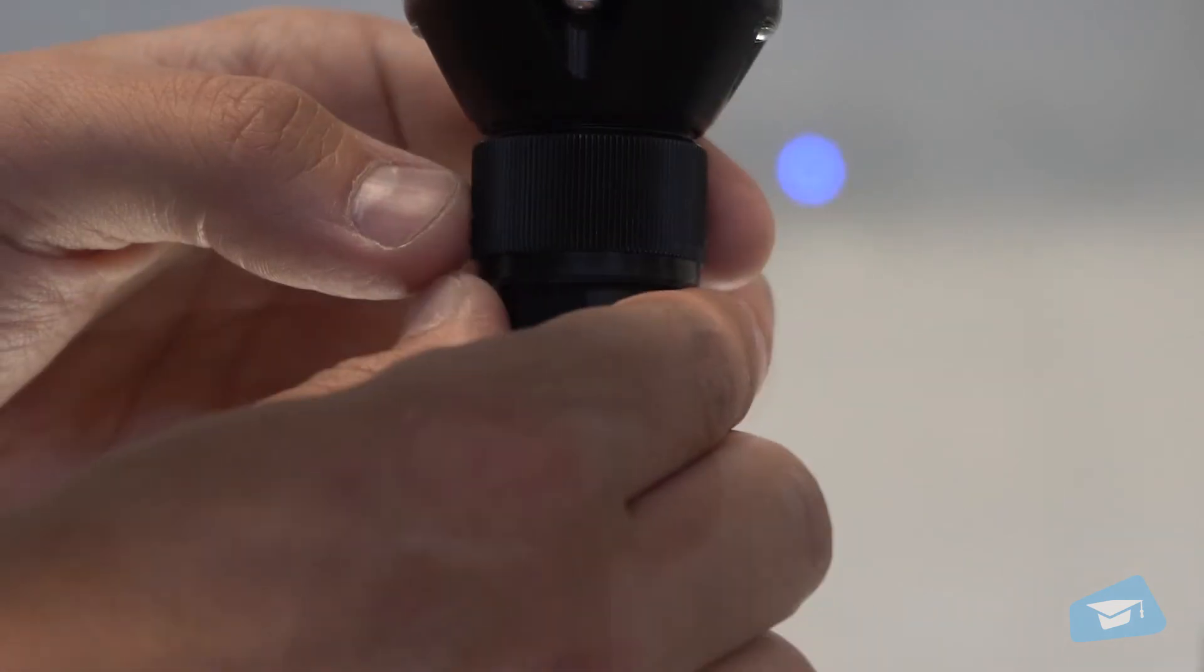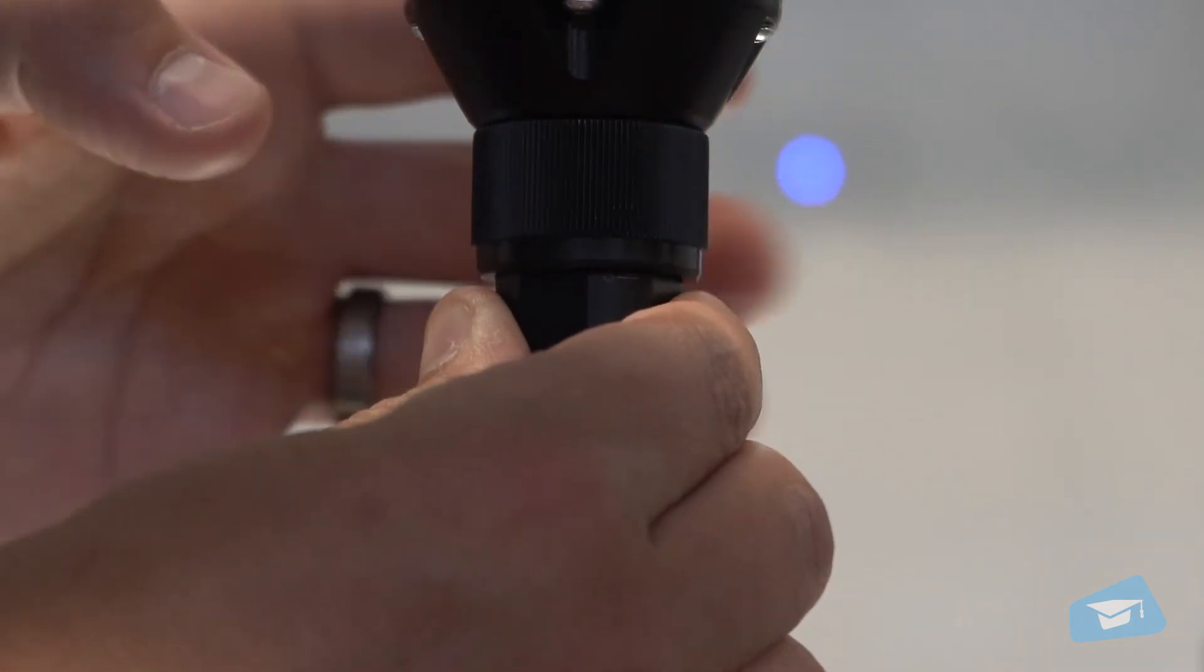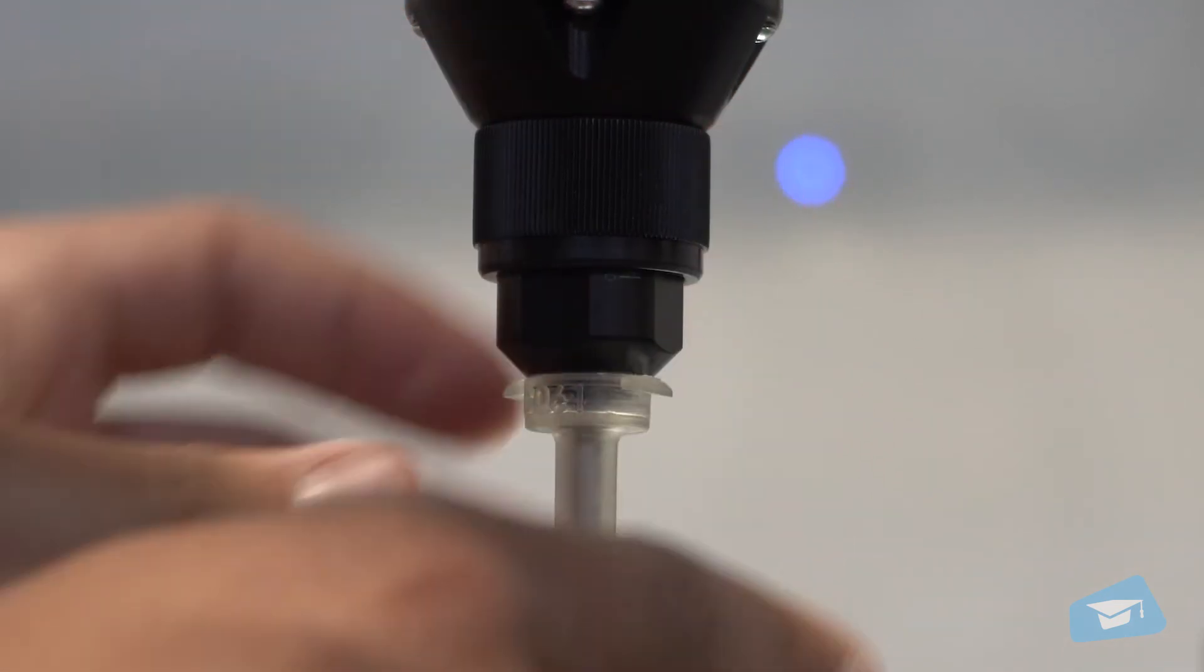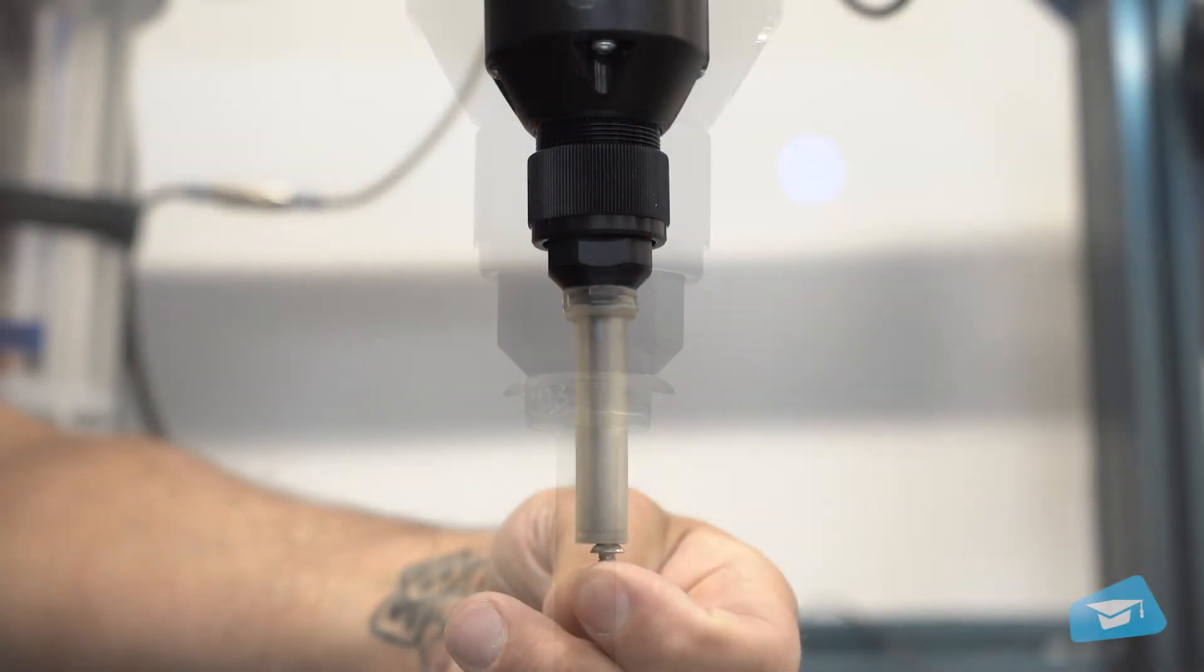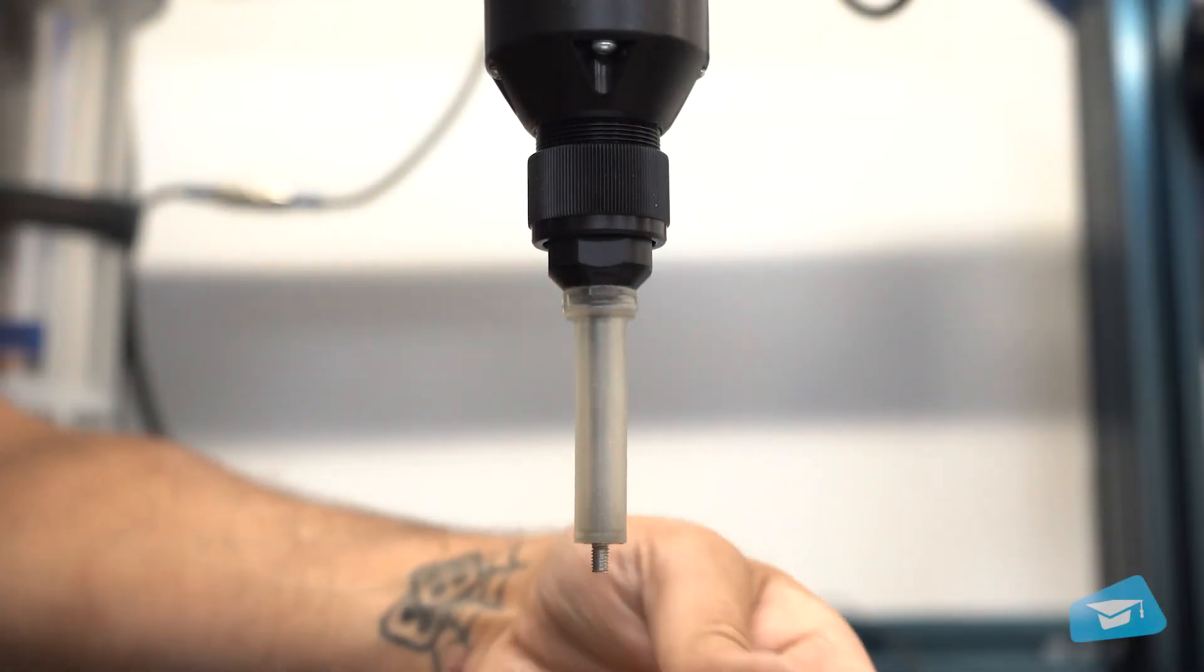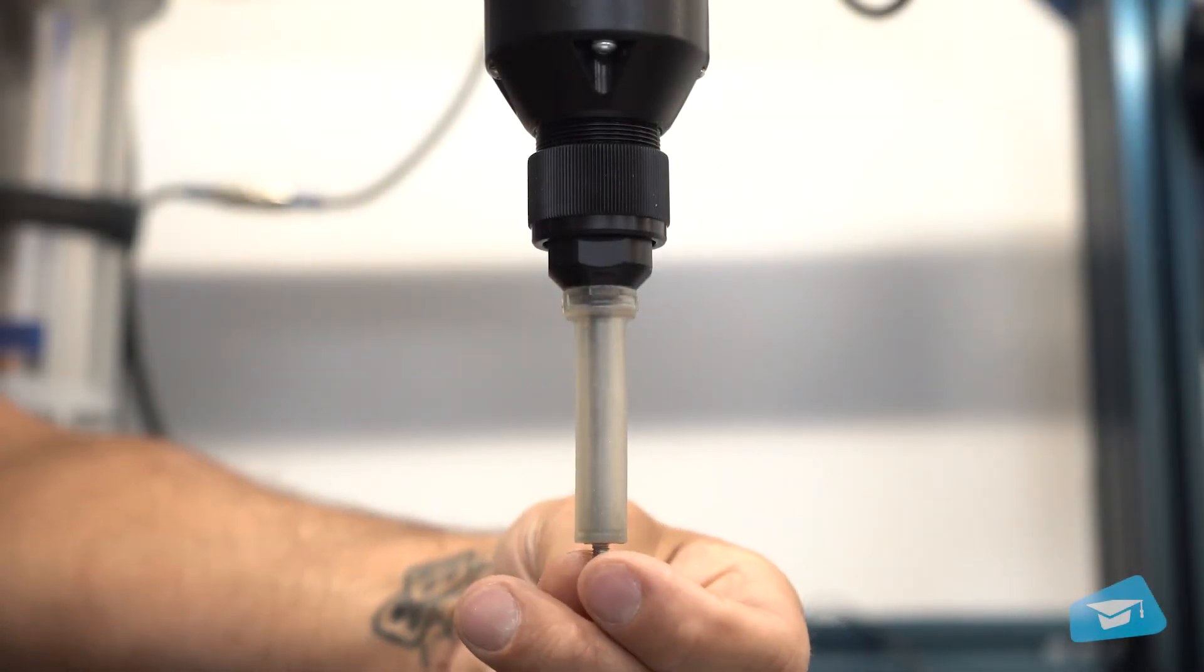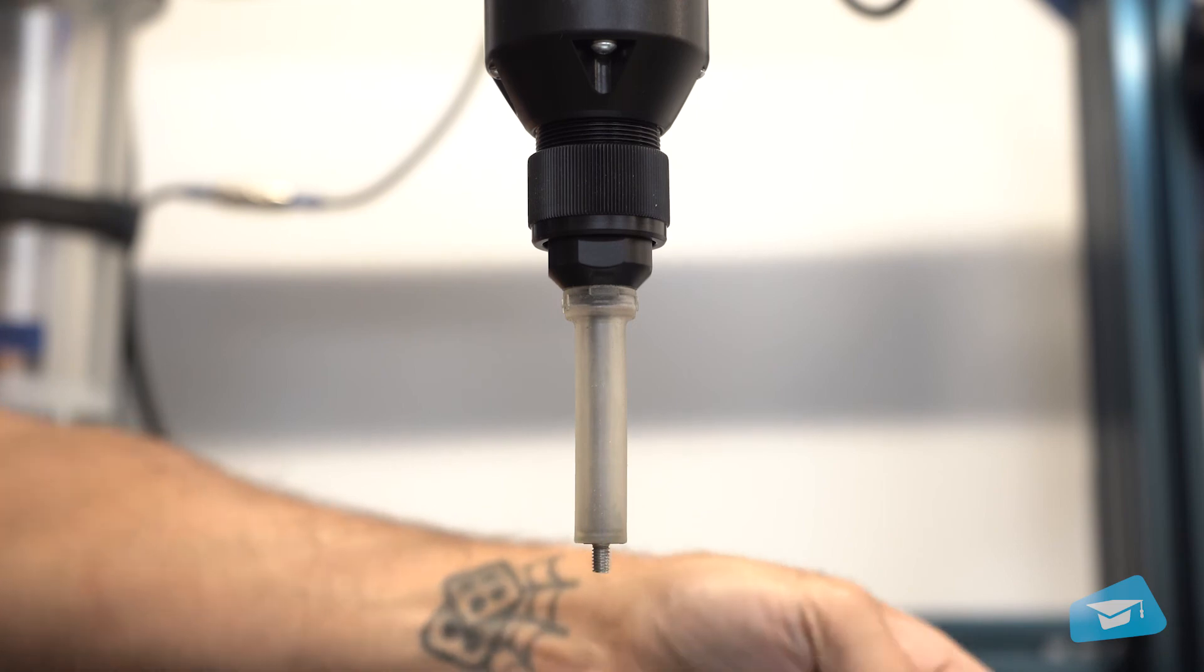Tighten the coupler locking nut to secure the vacuum sleeve and avoid air leakage. You should now be able to take screws consistently with the vacuum system.